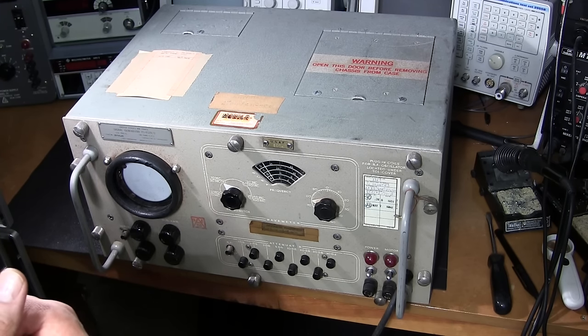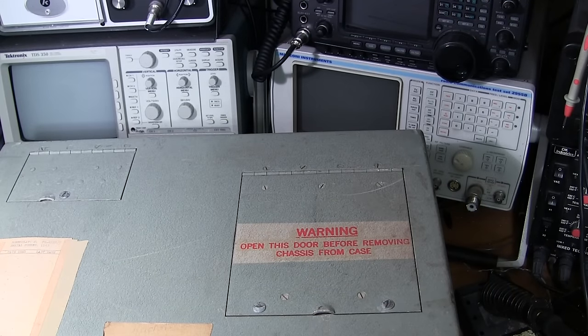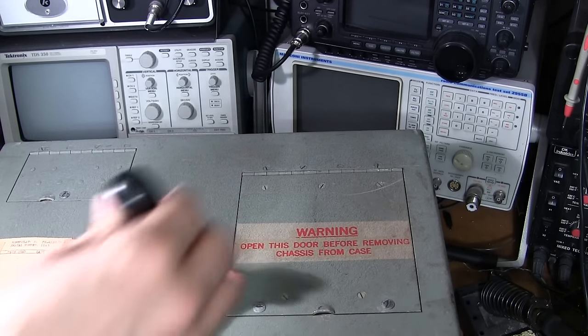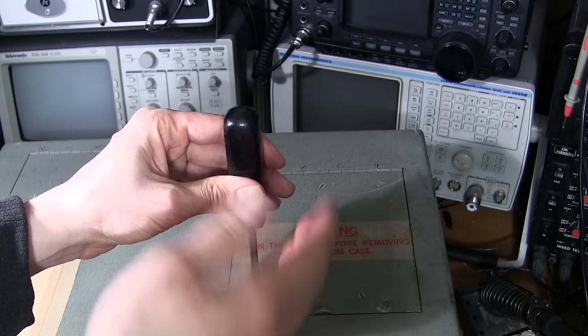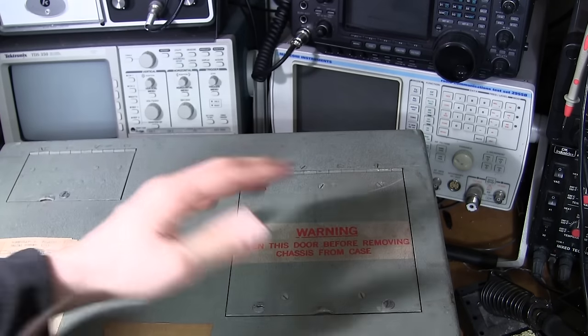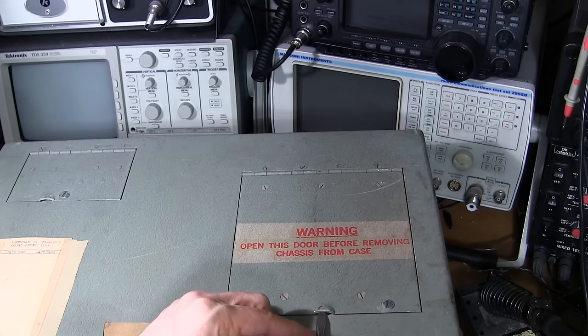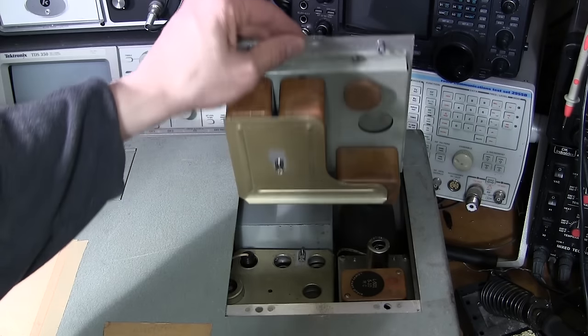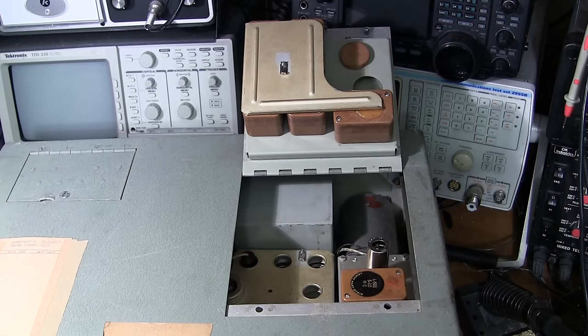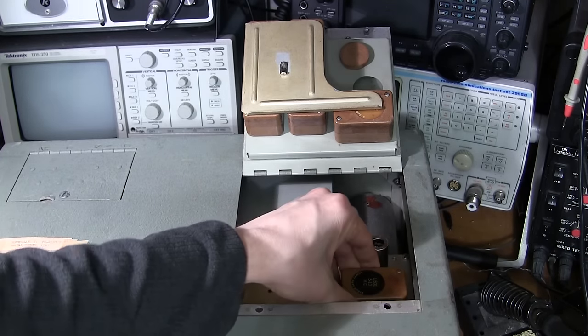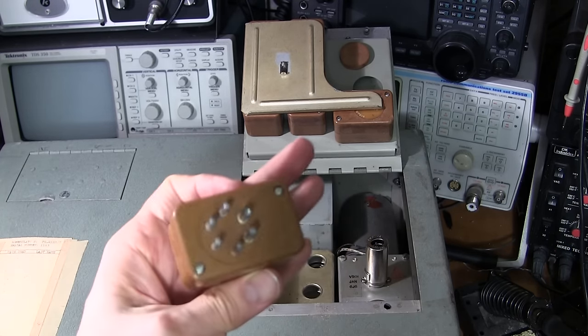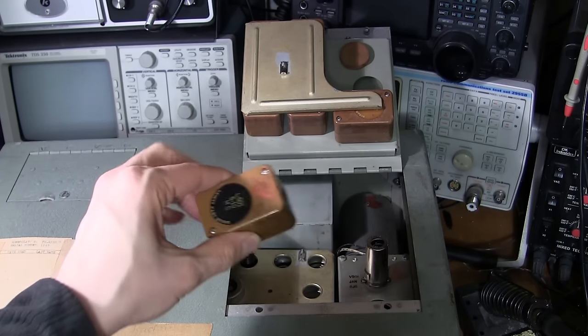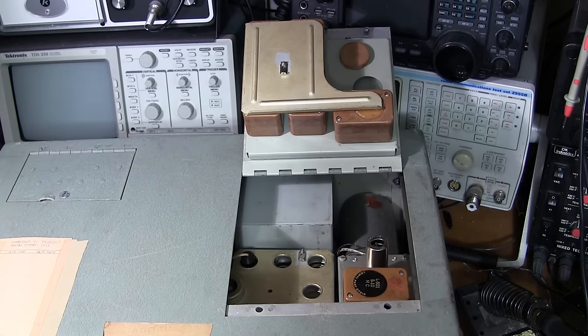In order to get into the service doors you have to put a screwdriver in these things and give them a quarter turn to snap into place. So that's open so I can open the door now. Inside we have all the coils that set the sweep range of this unit. There's one coil installed right here right now, you can pull this thing out. It has an old tube base on the bottom and that plugs into a socket here, and under here we have all the other coils for all the different ranges.